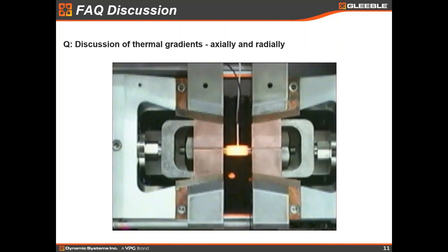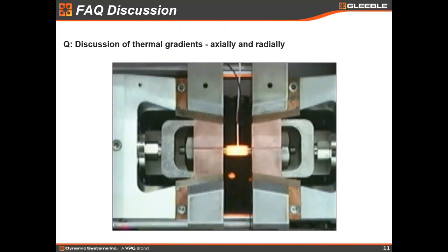This sample video shows the effect of time on thermal gradients. Joule heating heats the sample uniformly over the entire bulk of the sample, so the ends heat at the same rate as the center. However, heat extraction is a time-dependent phenomenon — heat will start to soak out of the ends into the water-cooled grips. The initial heating starts and the ends of the bar are very hot; the temperature is being controlled by the thermocouple in the center. As we heat at a very fast rate, the entire bar heats up. Then as we reduce the heat to maintain a constant temperature, those ends start to cool off. You may need a few seconds hold time at peak temperature to let the sample equalize and let the thermal gradient stabilize before you continue with your experiment.